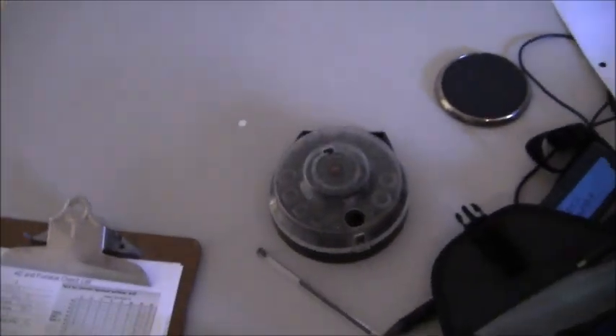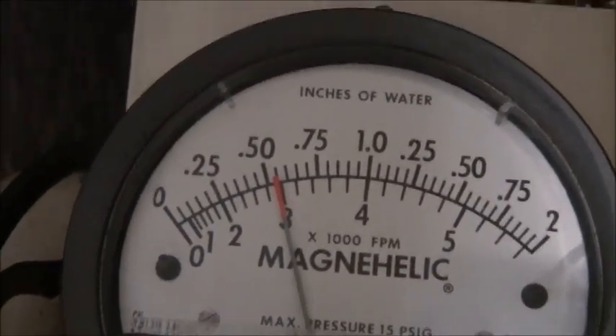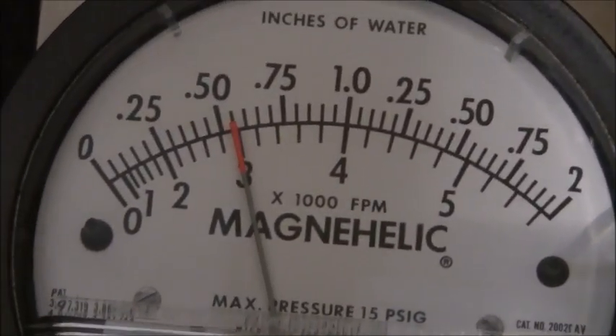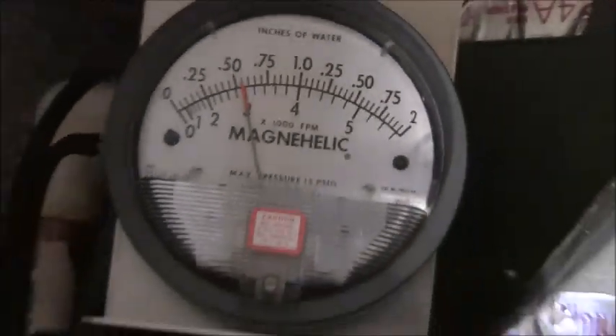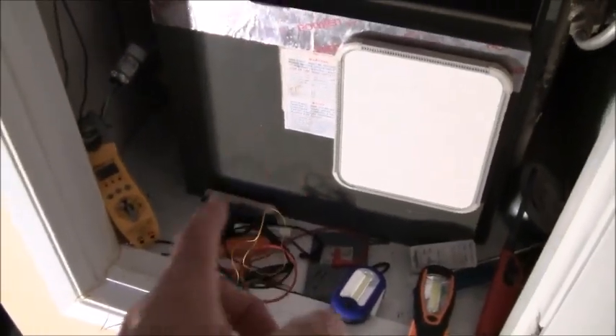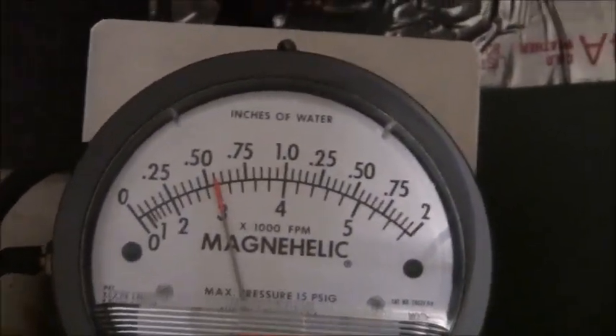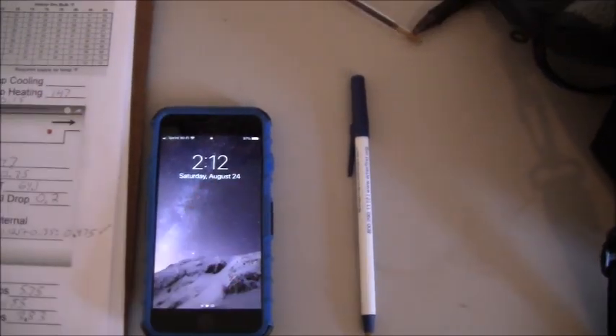Let me get a time here. Time is 2 o'clock. So I need to wait to at least 2:10 in order to have the refrigeration cycle settle down and see what's going on. But while we're here, let's go ahead and check our external static pressure. It looks like it's come up just a little bit, and that is probably due to the supply fan going at a faster speed. That probably has increased the external static pressure just a little bit. So we're okay, and we're still close to a half inch of static pressure there. Okay, it's been 12 minutes.